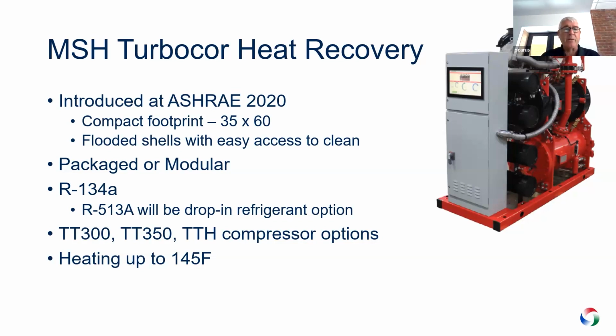We can do this application with Danfoss's TT300 and 350. If you don't know the nomenclature, those are just their standard lift compressors. But the TTH machine, available in 130 tons, is actually their high lift machine. So you're able to do more lift and continue to maintain those hot water temperatures up to 145 degrees Fahrenheit with that machine. We can also do a very large flooded shell machine. I didn't put that in here, but we can do that up to a 15-foot barrel. The largest one of those we've done in a single machine is 800 tons. So lots of choices for water-cooled applications.